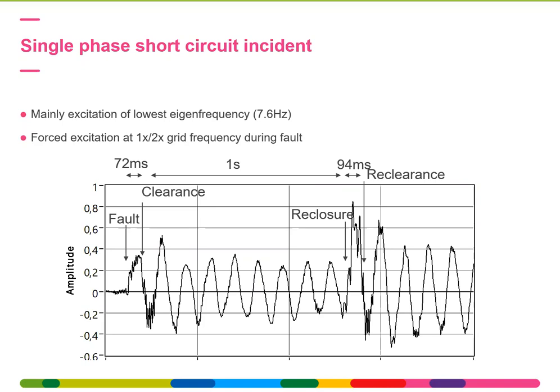Once the fault appears, which lasts 72 milliseconds, you excite at 50 and 100 hertz in this example, so once and twice grid frequency. And then you have the lowest torsional vibration eigenfrequency, which is excited, here more or less 7 hertz with an amplitude of maximum 0.5 degrees. A second reclosure is attempted 1 second later, but again there was an issue, a new short circuit, because the crane was again too close, and the amplitudes are even larger in this case.